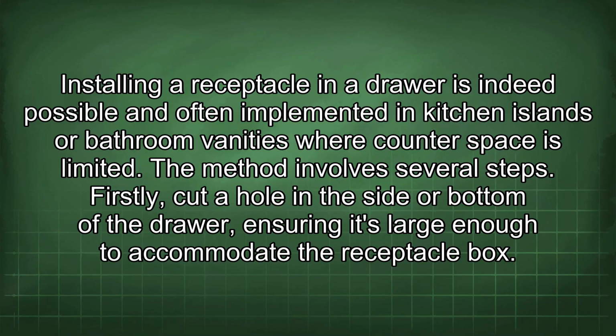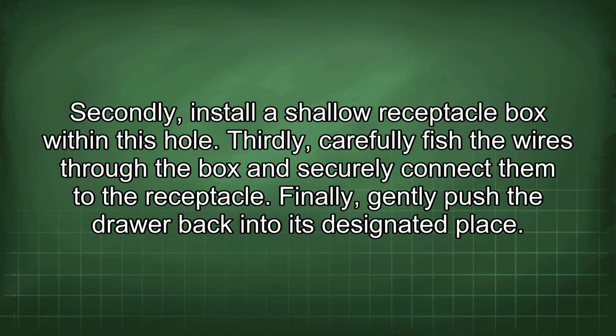Installing a receptacle in a drawer is indeed possible and often implemented in kitchen islands or bathroom vanities where counter space is limited. The method involves several steps. Firstly, cut a hole in the side or bottom of the drawer, ensuring it is large enough to accommodate the receptacle box. Secondly, install a shallow receptacle box within this hole. Thirdly, carefully fish the wires through the box and securely connect them to the receptacle. Finally, gently push the drawer back into its designated place.